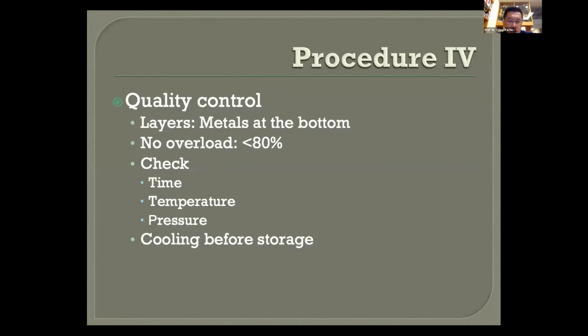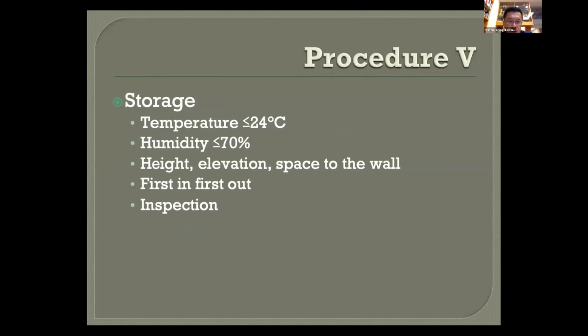So during the sterilization process, we have to check the time, how much time we have spent with the process, and whether the temperature has always been kept at the desired range. And the pressure as well. So after the sterilization, we have to cool down the items before we go to the next step of storage. We have a separate space for the process of storage. We keep this space with temperature below 24 degrees Celsius and the humidity below 70%.